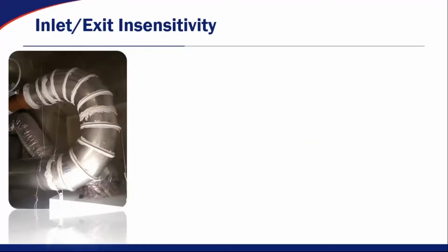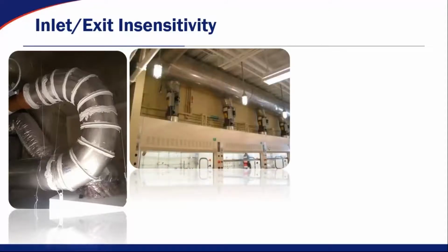Inlet and exit insensitivity inside of a building is important not only for a new building, but also if you're trying to do retrofits. So for a new building, these are some pretty challenging installs where if you're trying to get a straight duct run to measure airflow, it would be very challenging. So this is a 180-degree bend inside of a ductwork. Obviously, not really a good place to put a flow sensor inside that installation.